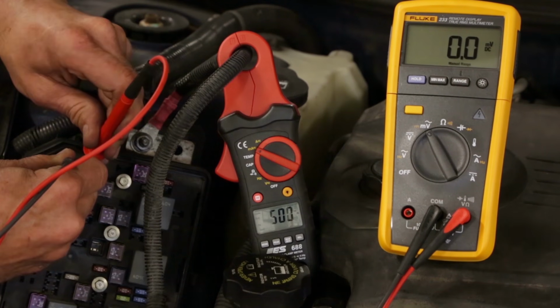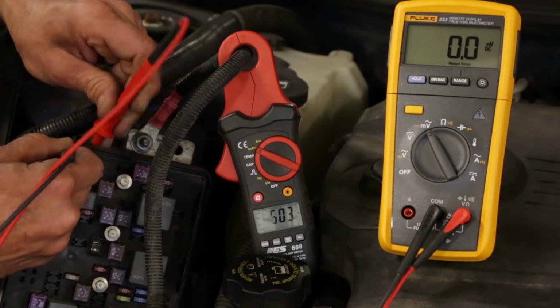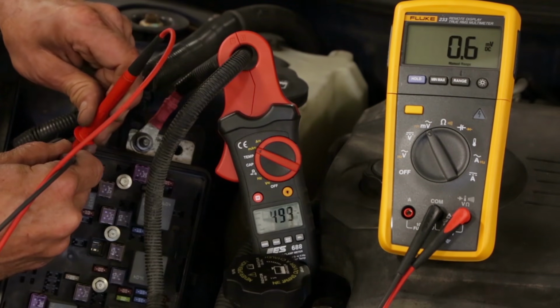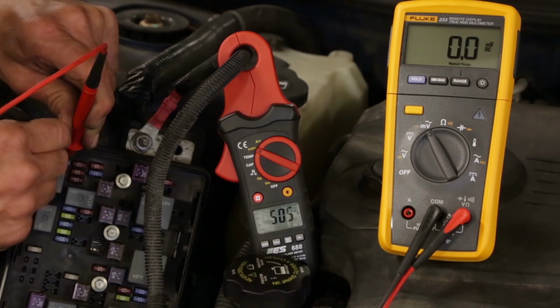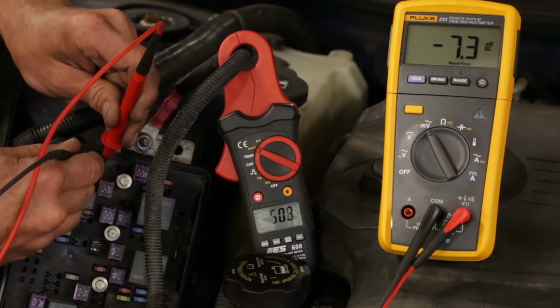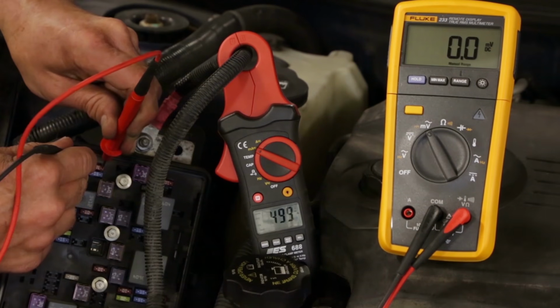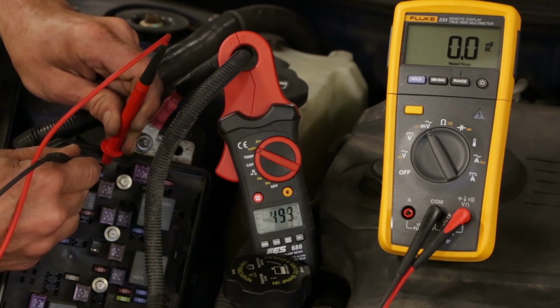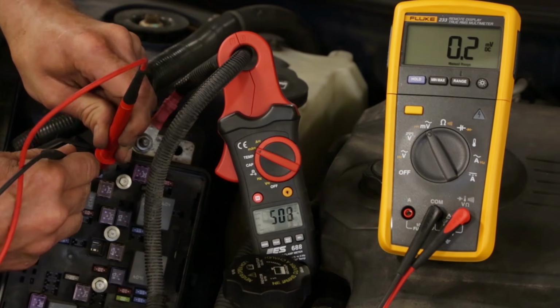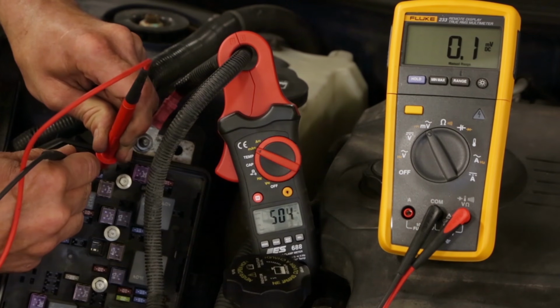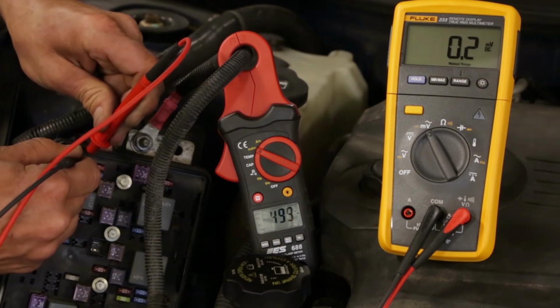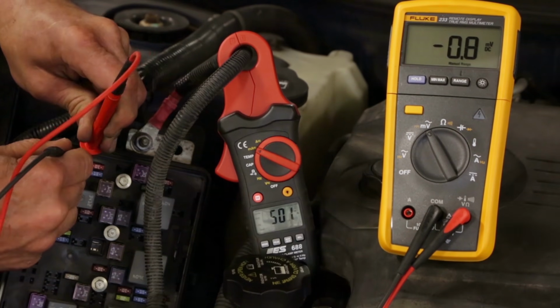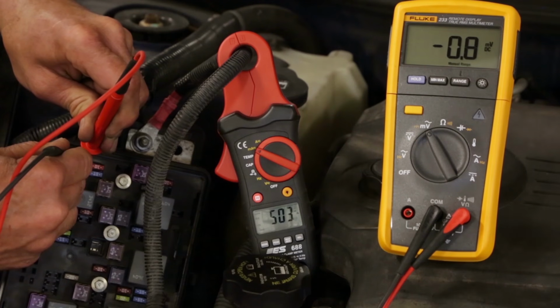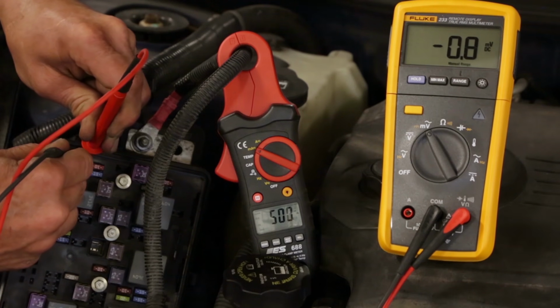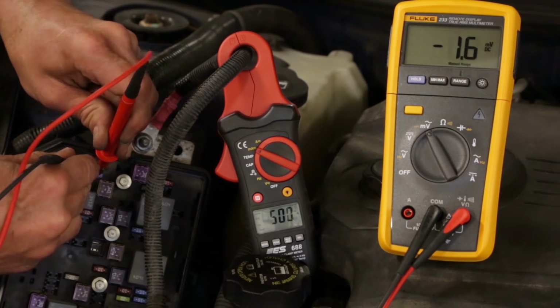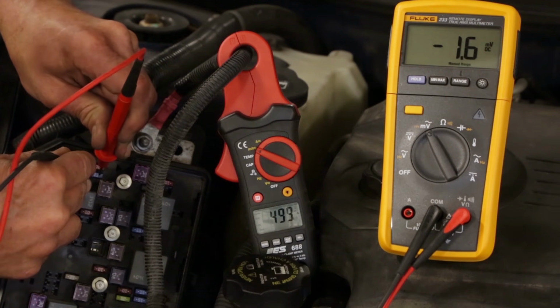I'll check this next fuse. That one's dead 0. I'll check this one. This one gives me dead 0. 0 over here. Now there I'm showing 0.2 millivolts, 0.1. And there I have a fairly high draw of 0.8 millivolts. So I've isolated this down to 2 fuses that have a fairly high voltage drop.